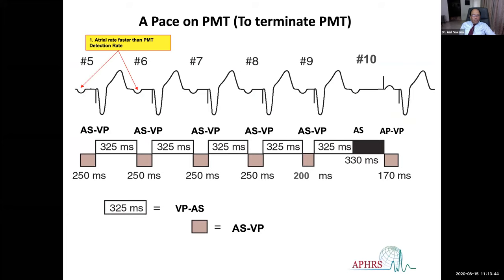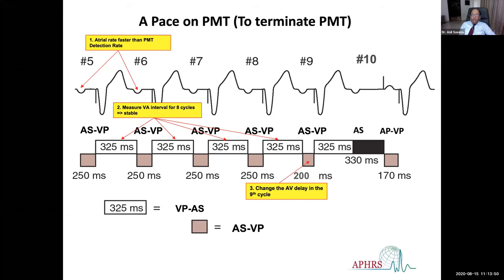When the patient is having PMT, after a certain number of counted intervals, the pacemaker makes a diagnosis that it's a PMT going on. Instead of giving a ventricular pace upon sensing the atrium, it gives an atrial pace, and that restores the normal rhythm.